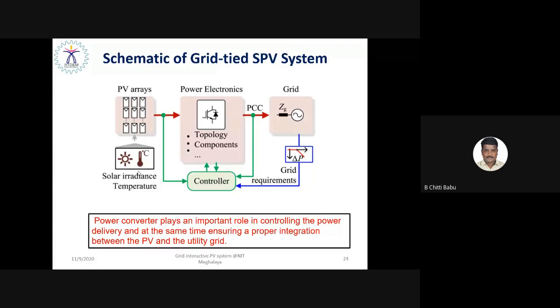Let's talk about the schematic of a grid-tied solar PV system. The PV array is composed of PV modules in series-parallel combination. The input parameters to the PV array are basically solar irradiation and temperature, and that light energy will be converted into electrical energy. That electrical energy is unregulated or uncontrollable, right? So it has to be interfaced with the grid via a power electronics converter, as it is a candidate that provides an asynchronous interface. The power electronics converter has different topologies as well as components, and according to the topology and components, it can integrate the solar PV system with the utility grid.